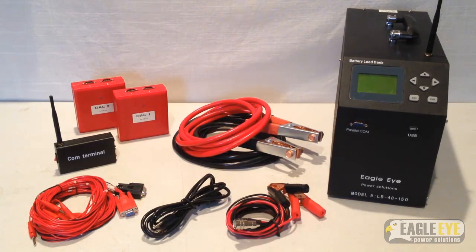Shown are the main components of the load bank. The LB48150 DAC comes with the following components: a set of discharge cables, which are used to put the load on the batteries during the test; an AC power cord; voltage test leads, which are used to display total string voltage; DACs, or data acquisition cases, which display and monitor voltage on a cell level. The number of DACs used depends on the model and application.